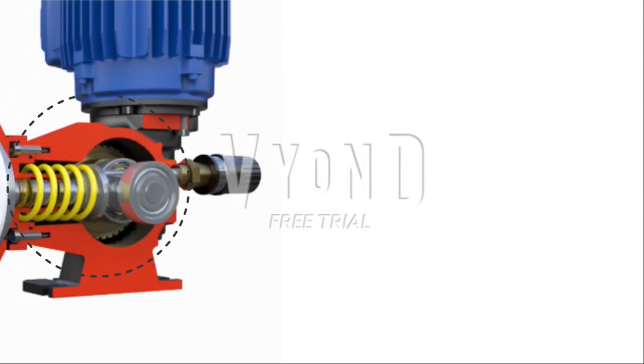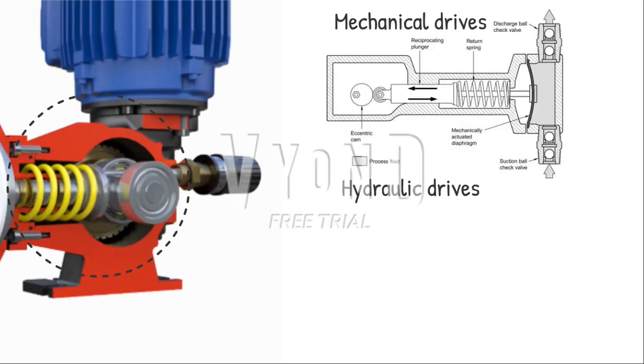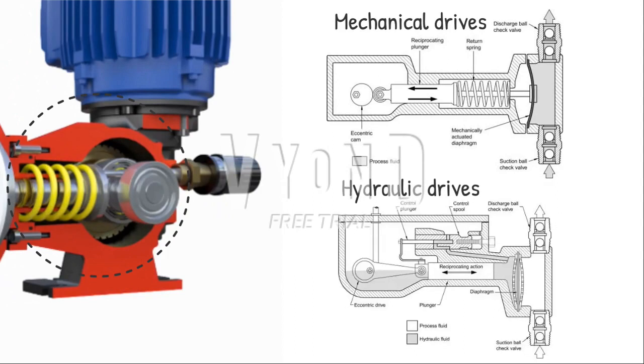Diaphragm pumps come in two varieties: mechanically and hydraulically operated. Mechanical drives are simple and inexpensive, but are only appropriate for very mild duty applications due to their short diaphragm life. Hydraulic drive diaphragms can be single or double; a single unit is the most typical for the majority of services, while a double diaphragm may be required for particularly hazardous services.